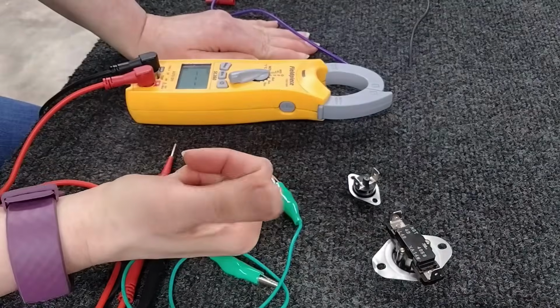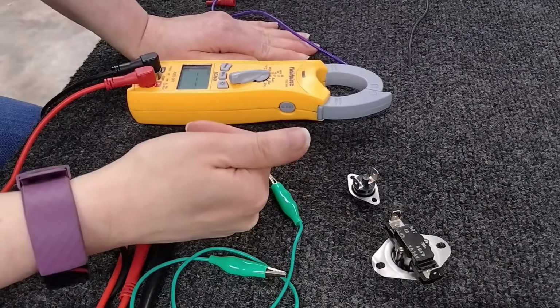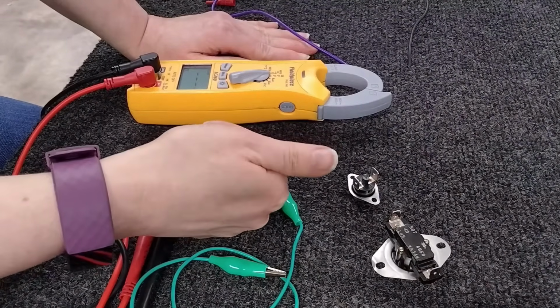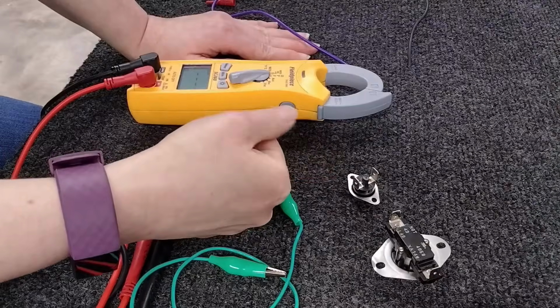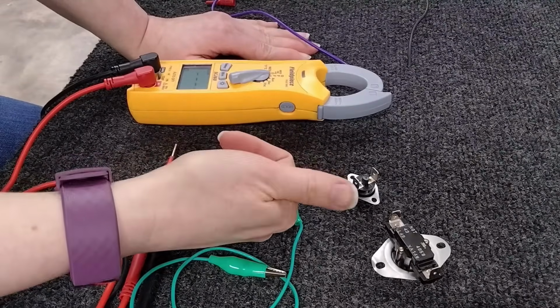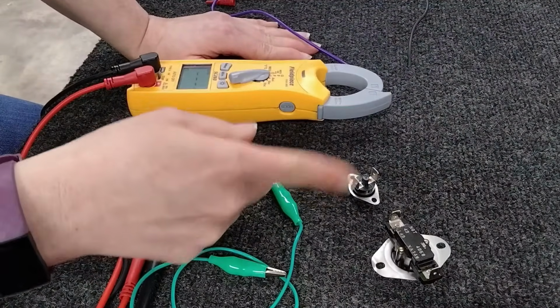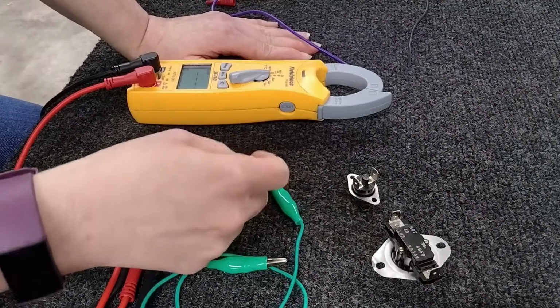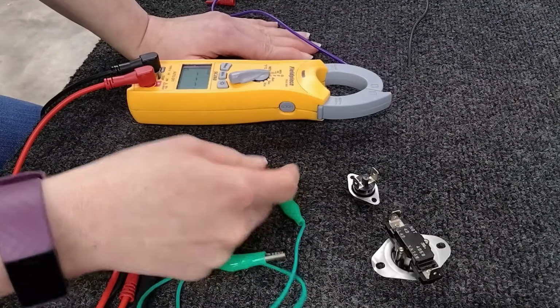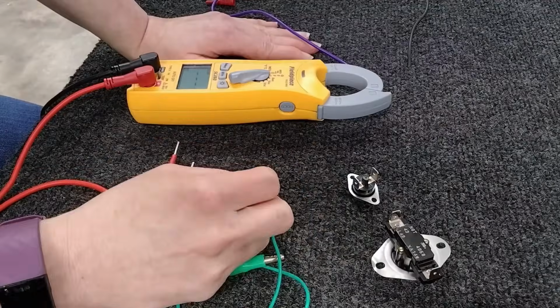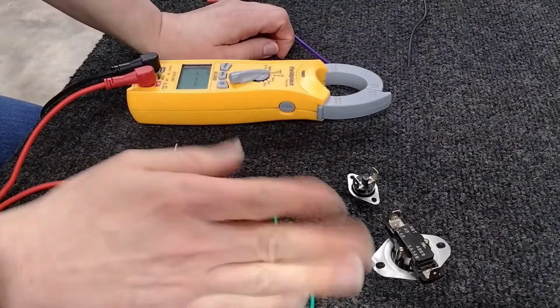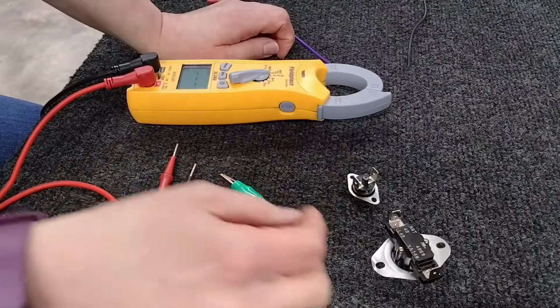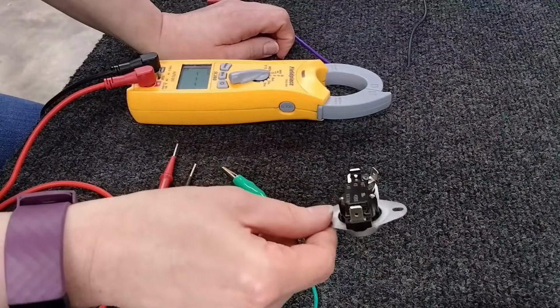Most units on the blower housing have a safety switch. You need to make sure that that safety switch is depressed, whether you tape it, or have someone hold it down, before you turn the thermostat to heat. Or for some of you guys that are comfortable with jumping R to W for your heat at the board, you can do that. After you have it jumped around, unfortunately the only way to see which limit is bad is to bypass each and every one.